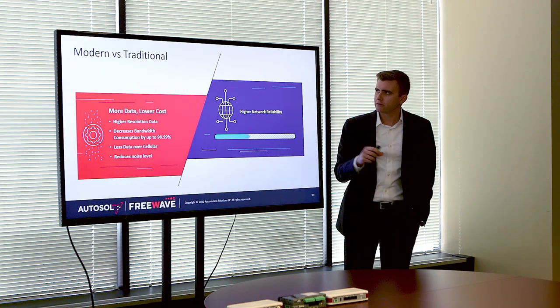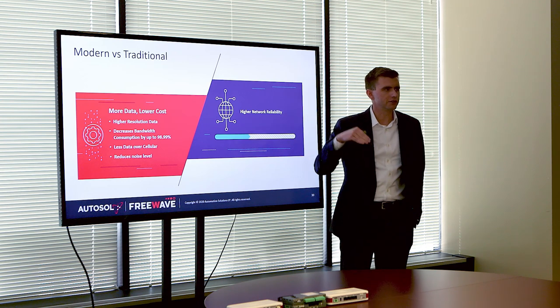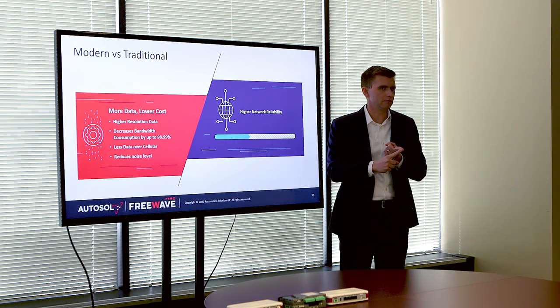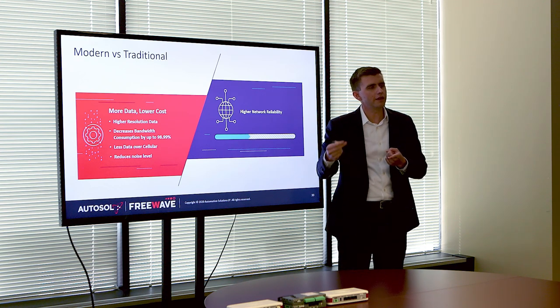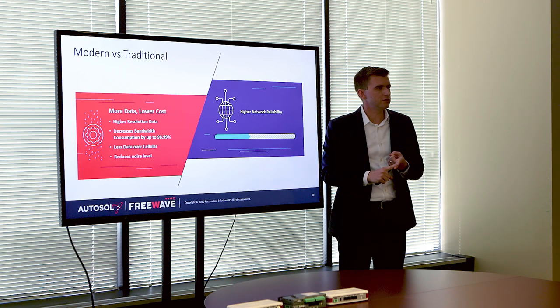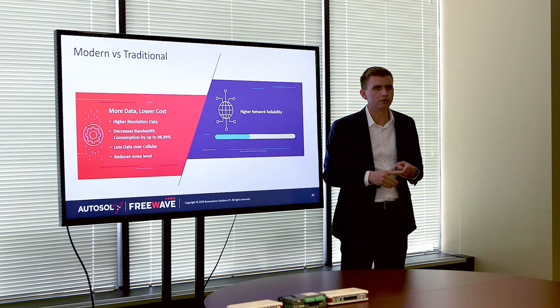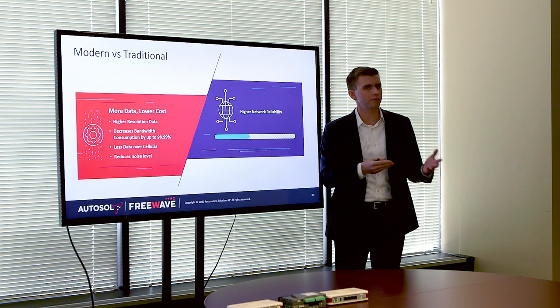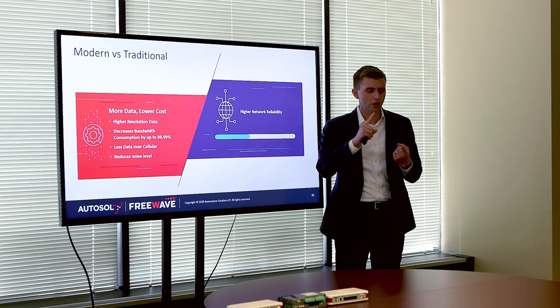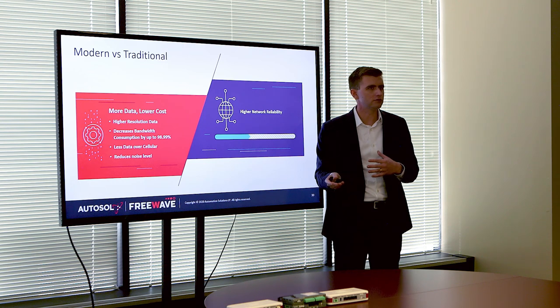To really talk about the benefits of modern versus traditional SCADA: the first is reduced bandwidth consumption. Because we're handling data for SCADA purposes on the edge, we can reduce bandwidth consumption with just basic MQTT report by exception, let alone fancy tricks with tag groups. This allows us to get higher resolution data for the tags that clients actually care about, addressing specific pain points and increasing production or reducing cost for gas or oil wells.